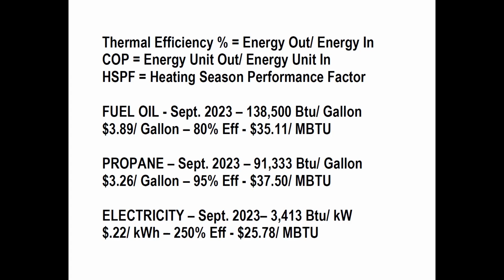What happens with oil boilers and furnaces is that as soon as it's cleaned and you start using it, it starts to deposit a little bit of soot onto the heat exchanger. And soot is a bit of an insulator. So you don't get as much efficiency of transfer between the products of combustion going out this way and the air or water flowing on the other side. Propane is better in terms of not losing that efficiency over the years.